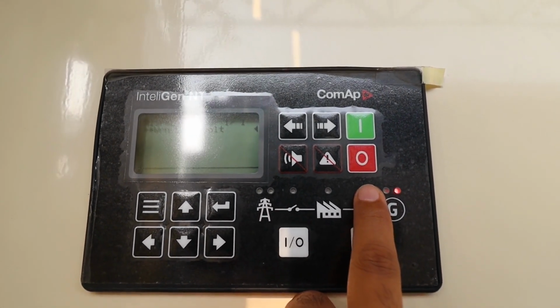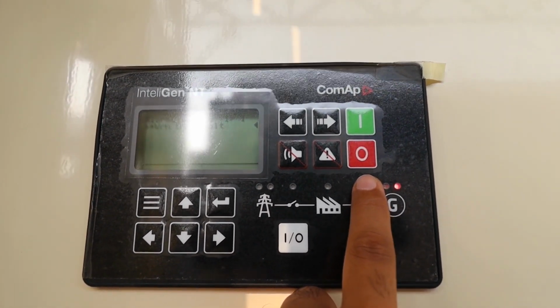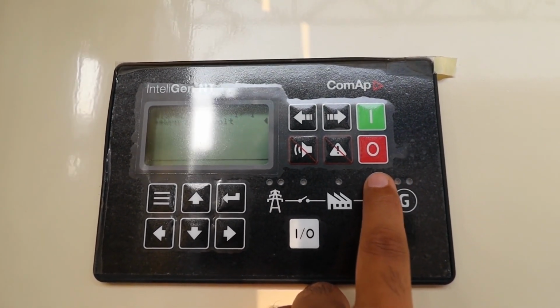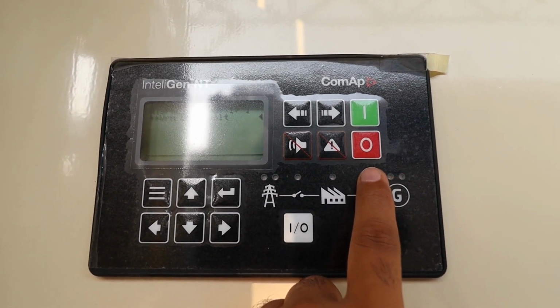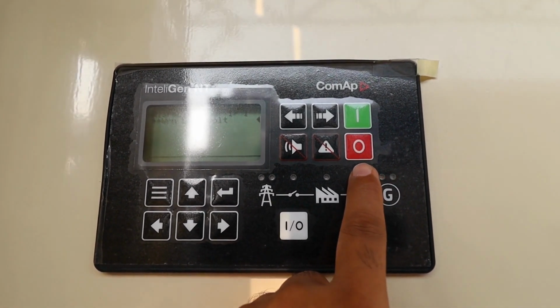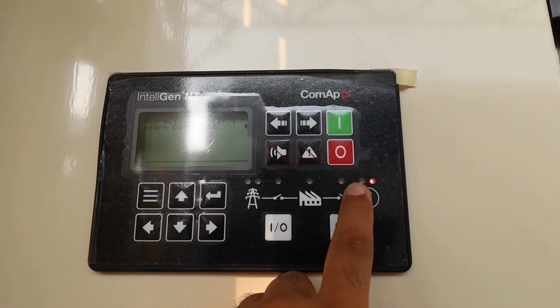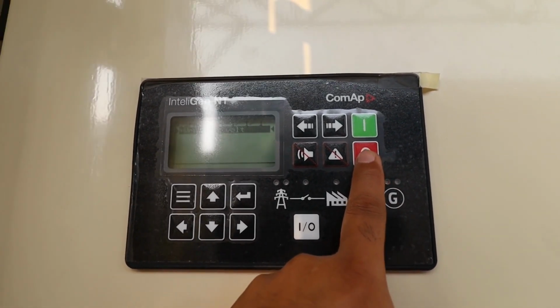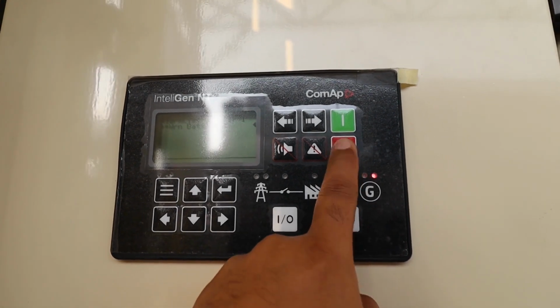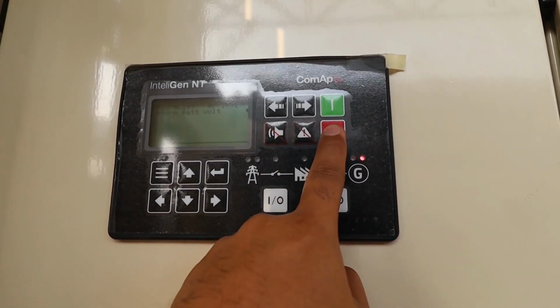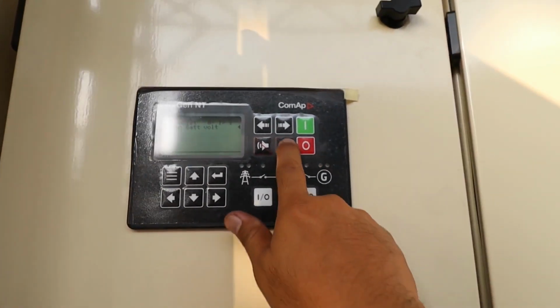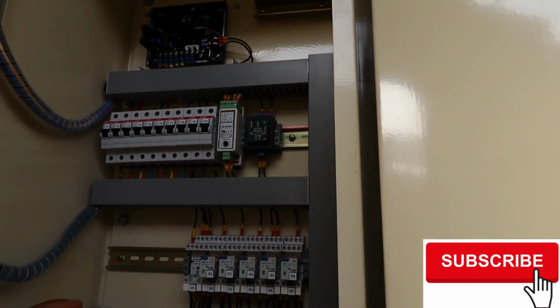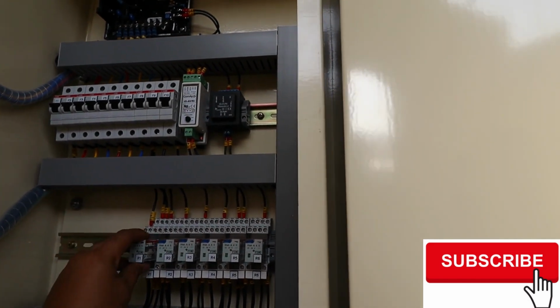It's saying warning battery low, it's okay, we can adjust that in our system, no problem for that. It means the voltage is brought down because it is cranking time. Okay, I'll just tap it for a while and then I will reset the alarm. Okay, for now I will connect that to our fuel relay, so it will fire up when we give the command to start.